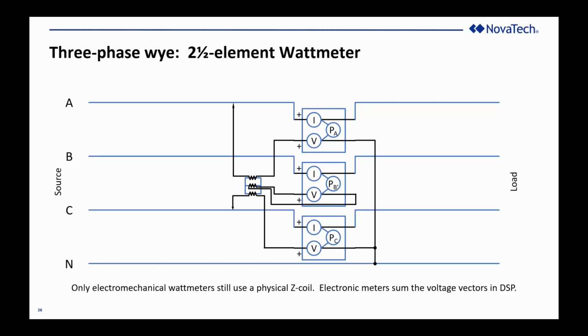and we multiply the synthesized B-phase voltage with the B-phase current. B-phase current still needs to be connected. So this is what's called a 2.5 element wattmeter. Notice that the terminology half element refers to an actual wattmeter that's only connected to the current. That's what makes it a half element. This is not the same thing as a 2-element. Well, I'm getting ahead of myself. We'll talk 2-element in the next couple of slides here.